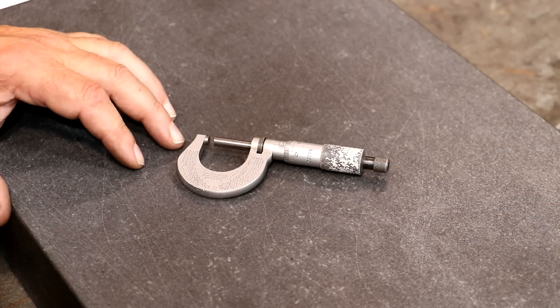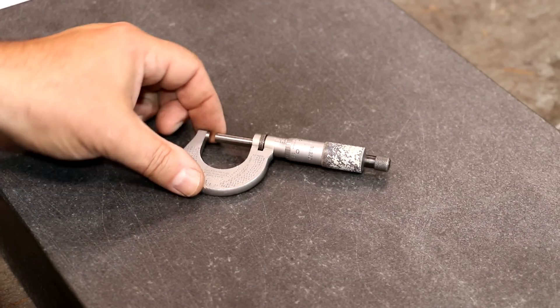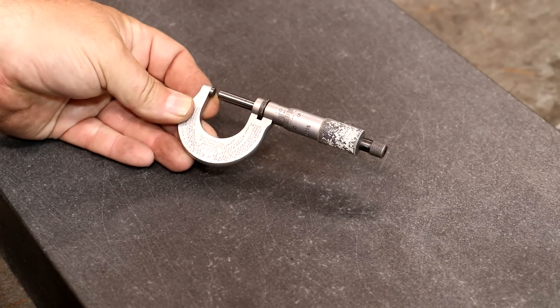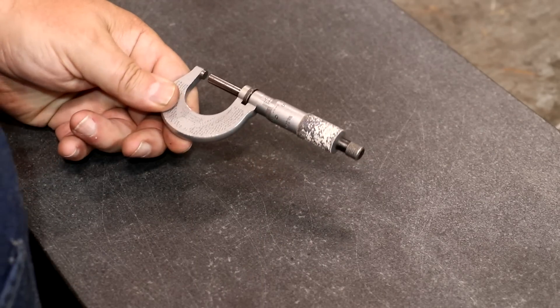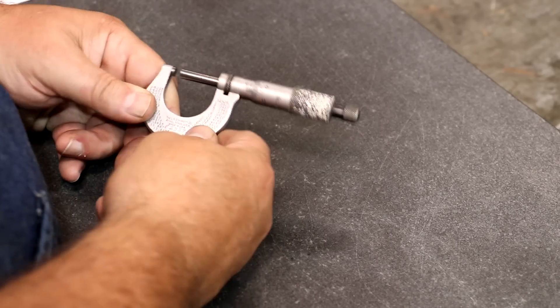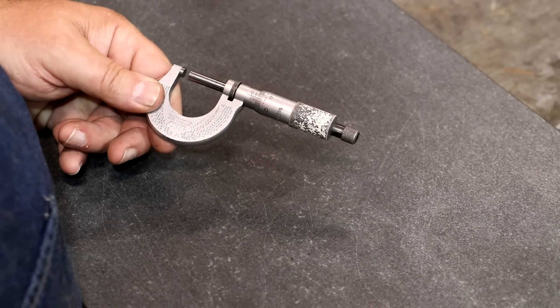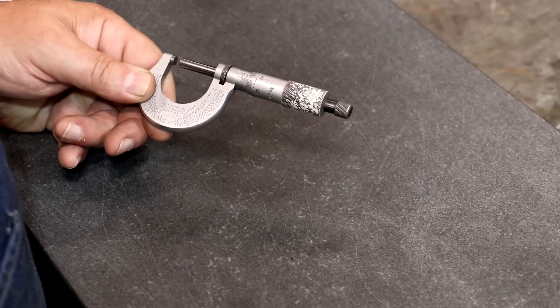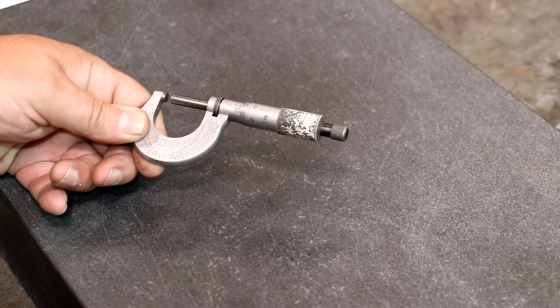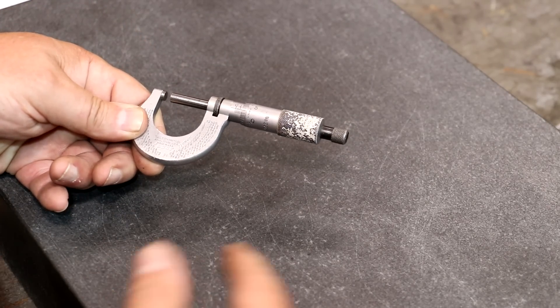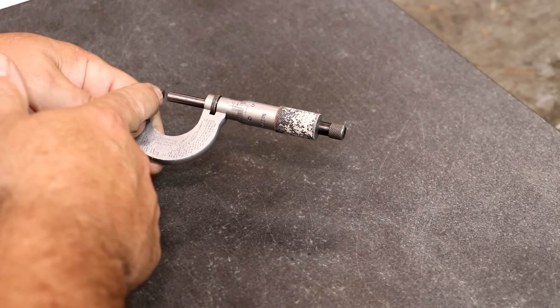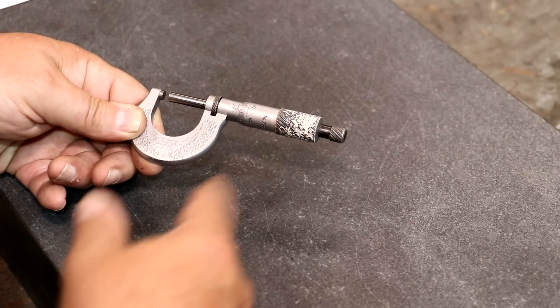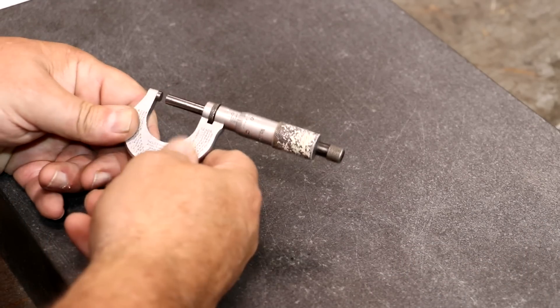So let's start with the easiest one that we're going to do here. And this is going to be the zero to one inch micrometer. This is a Starrett, very common micrometer. Anybody that's a machinist is going to probably have one of these in their toolbox. Most common one out there, because that's probably the most common range that people are machining in, to be honest with you. So on this one, you don't really need a standard because it's going to go all the way down to zero. And that's what we're going to actually calibrate off of is we're just going to run this down and see where it reads on the anvil.